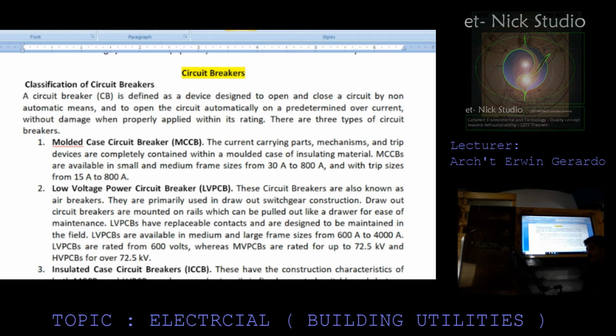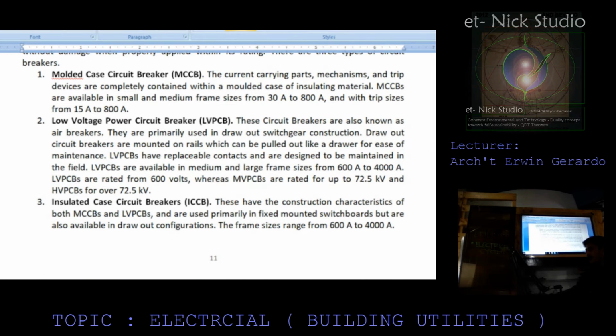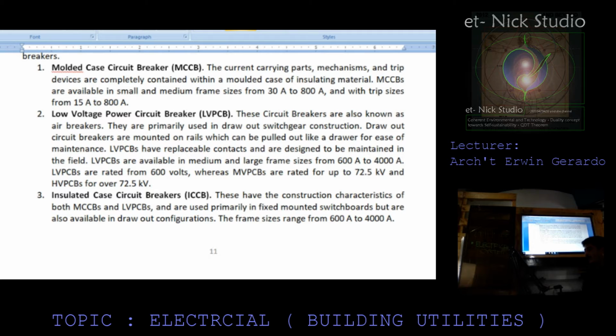Circuit breakers. Classification of circuit breaker. A circuit breaker is defined as a device designed to open and close a circuit by non-automatic means, and to open the circuit automatically on a predetermined overcurrent without damage when properly applied within its rating. There are three types of circuit breaker. Number one is the molded case circuit breaker. The current carrying parts, mechanisms and trip devices are completely contained within a molded case of insulating material. The MCCBs are available in small and medium frame sizes from 30 ampere to 800 ampere, and with trip sizes from 15 ampere to 800 ampere.